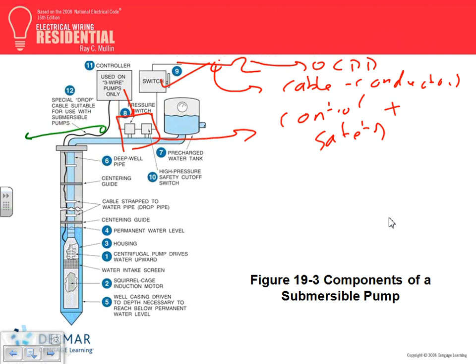What's wrong with this? Anybody know what's wrong with that? You know the impact on the impeller and the pump over time. You're going to kill the pump every time you open the faucet in your house, or you need water in the shower. So long story short, to regulate this, guys, make it easy on these pumps to work. Just work in stages. From here up, half an hour, we're done.